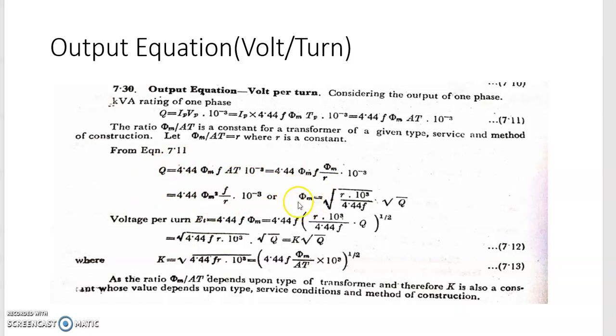So phi_M represents the maximum flux. The expression under the root involves r × 10³ / (4.44 × f) × KVA. The voltage per turn E_t equals 4.44 × f × phi_M. Replacing the value of phi_M in this equation, we get the volt-per-turn formula. Taking the constant terms together, E_t = k × √(KVA), where k involves the constant terms.